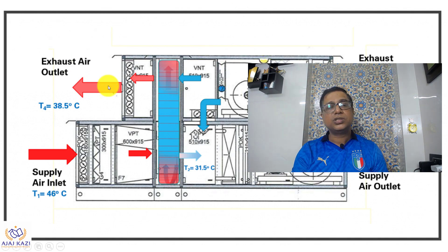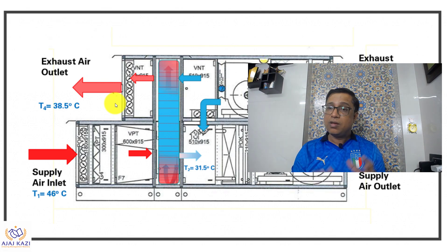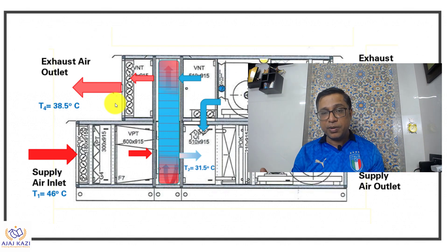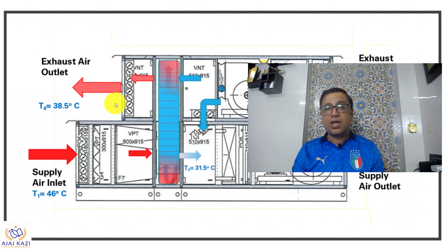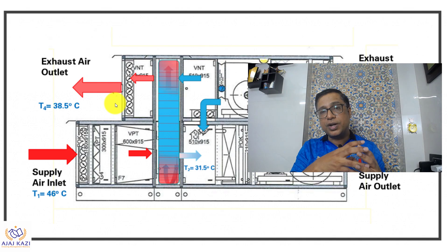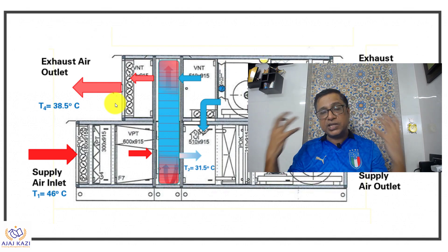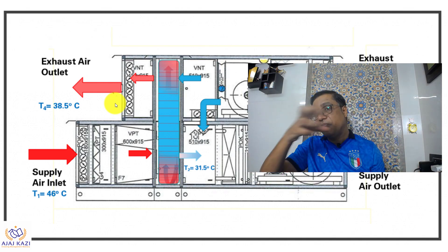When I talk about the supply side, we are in a conditioned area and we need fresh outside air. If there are many people, there will be an increase in carbon dioxide and there are a lot of VOCs. We need to take in fresh air to dilute the VOCs and the carbon dioxide. Depending upon the people and pressure guidelines, we need to take a certain quantity of fresh air.